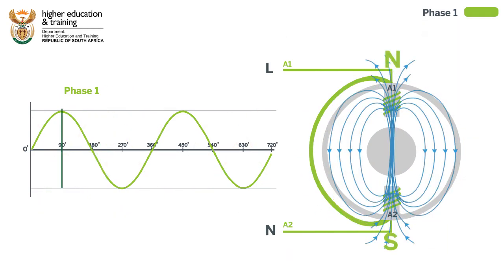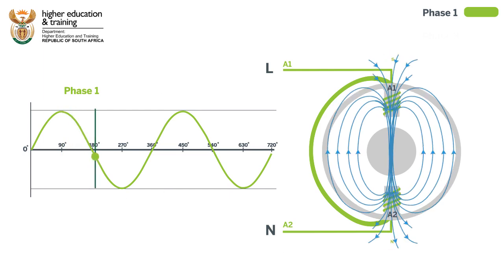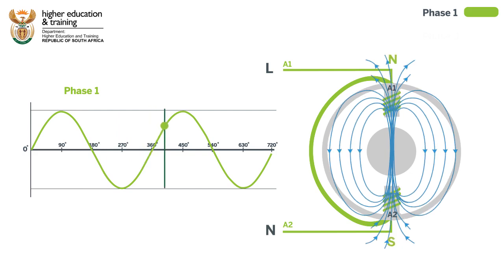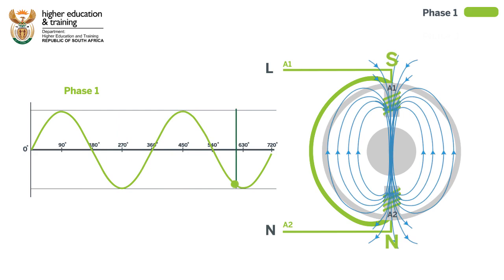With single-phase power, there is no second or third phase that is shifted out to produce this rotation. As the current alternates, all that happens is that the polarity of the stator field flips. There is no rotation for the rotor to follow.